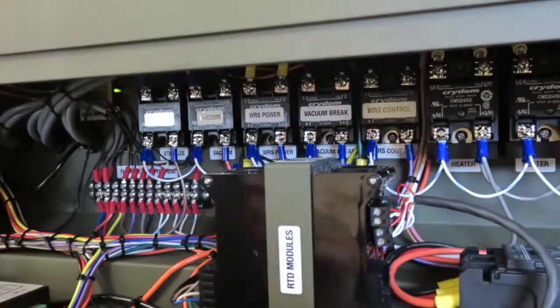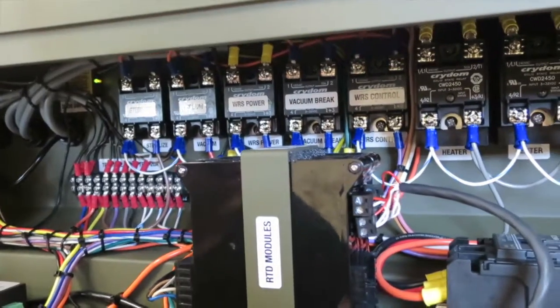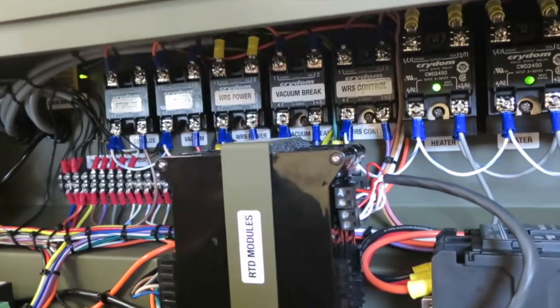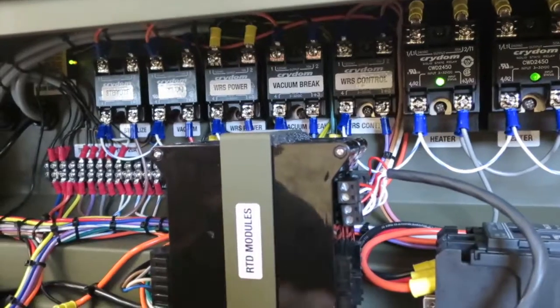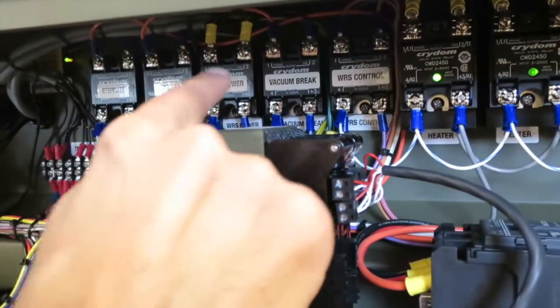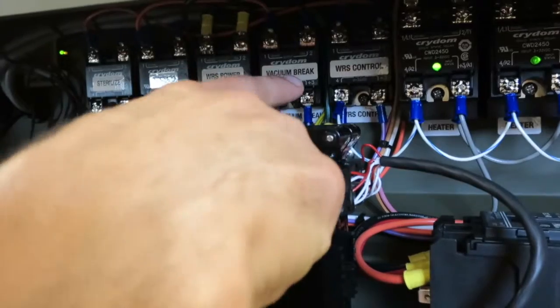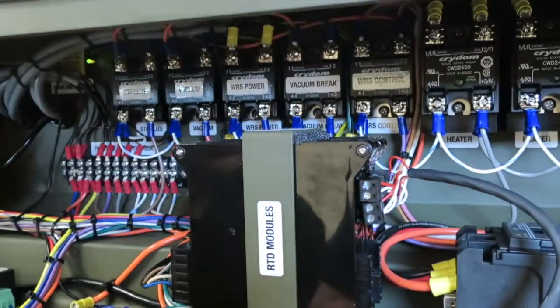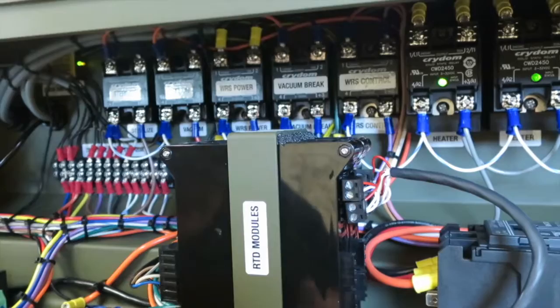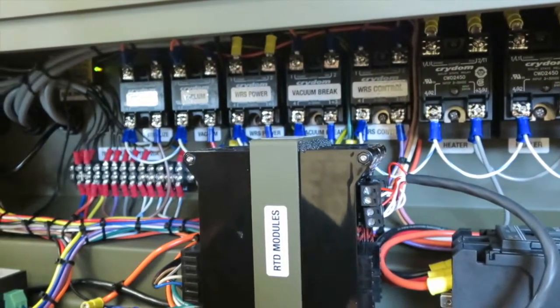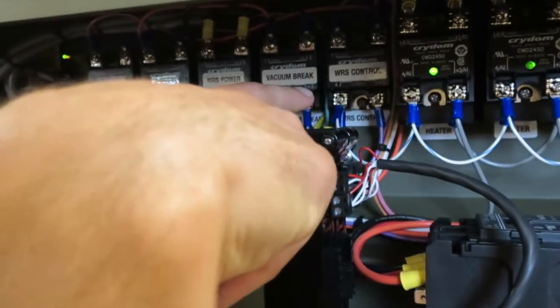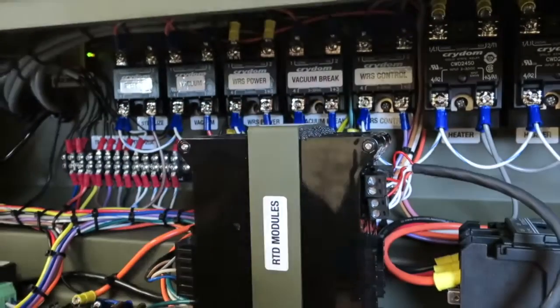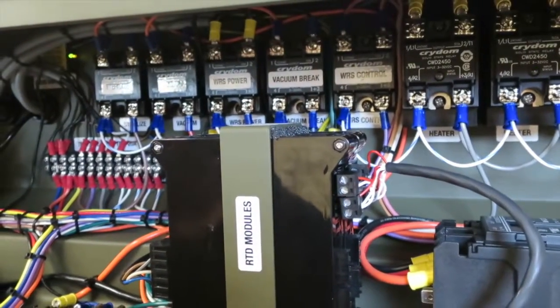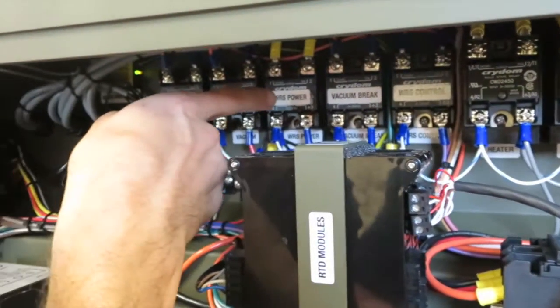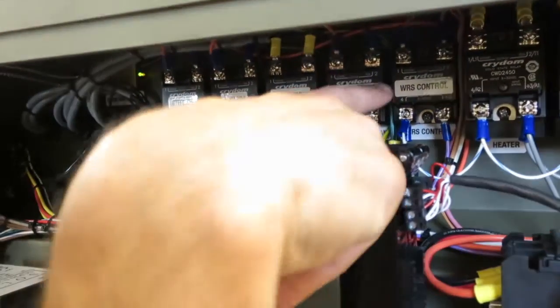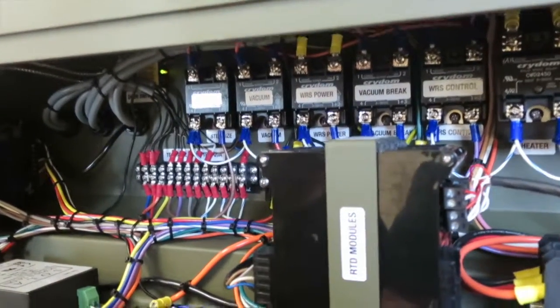The vacuum break valve, again, is on the other side that we already talked about. So whenever the cycle dictates to open that valve, the PLC will send 24 volts to that solid state relay. Finally, the water recovery system control. This is for during a cycle when the sterilizer needs to turn the water recovery system on. It will send power to this relay, which will turn the water recovery system on during a cycle. So again, this one is always on for the toggle switch, and that one is on for during a cycle.